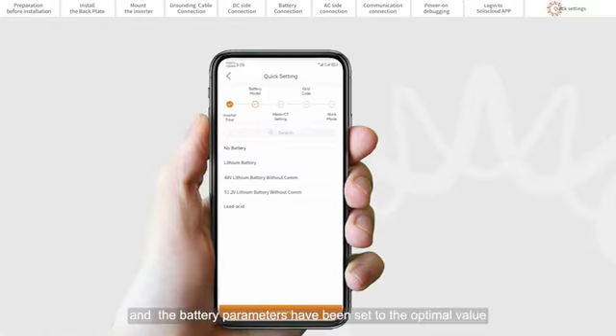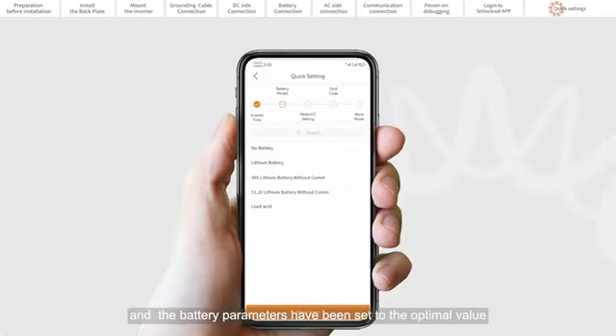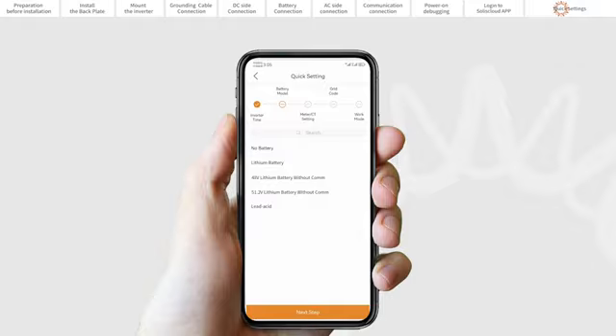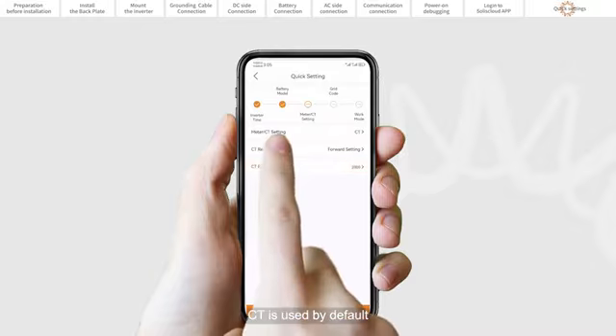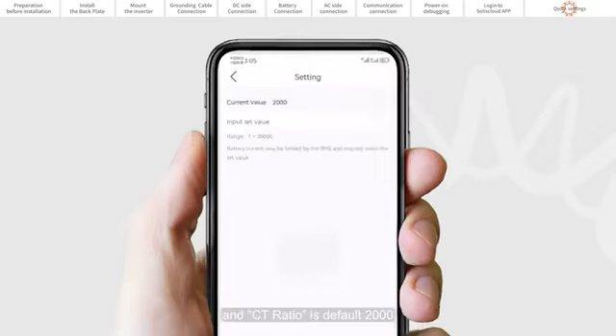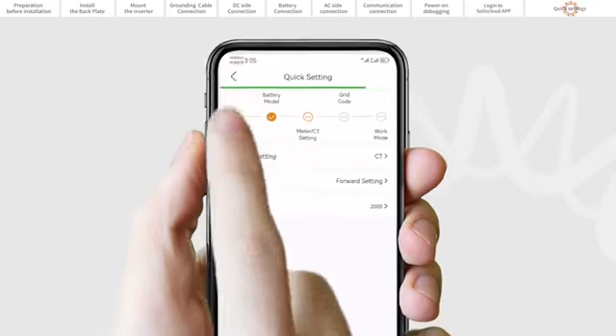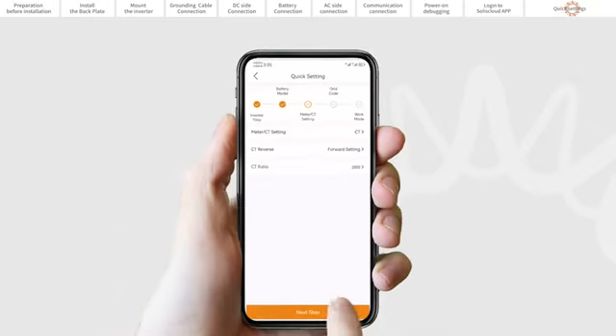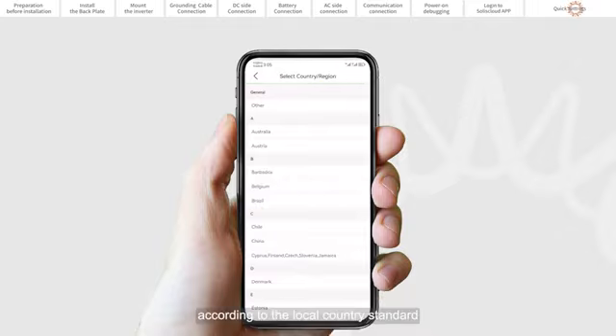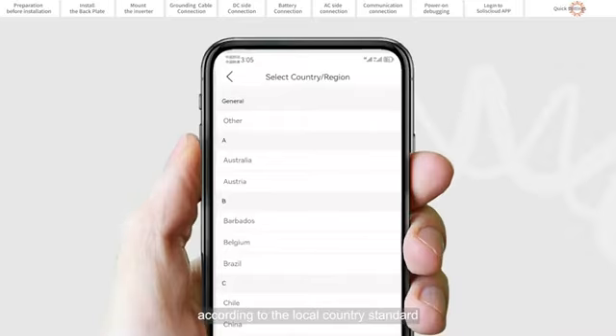The battery parameters have been set to the optimal value. You can set the battery capacity and charging or discharging current in the battery settings as required. For a lead acid battery, please select lead acid. CT is used by default, and the CT ratio is default at 2000 to 1. Set the grid code. Please select the grid code according to the local country standard.